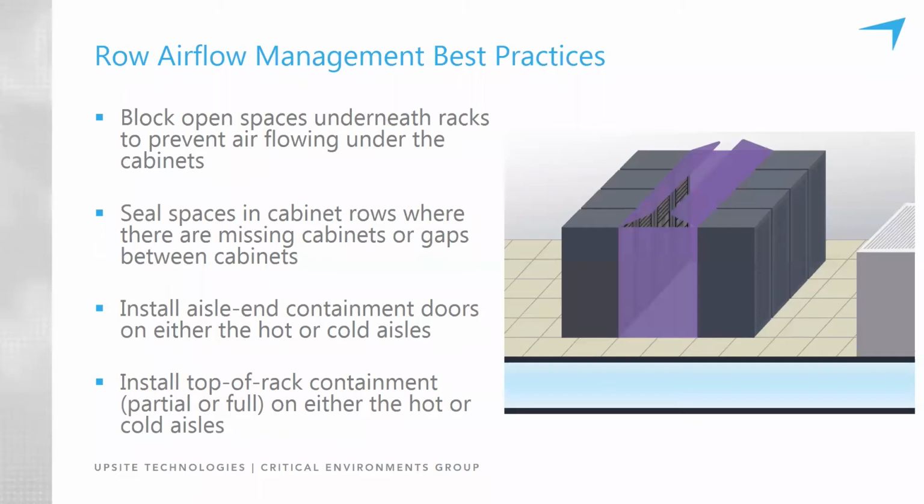And lastly, the top of rack containment. So hot aisle containment typically features an above rack barrier around the perimeter of the hot aisle and typically extends upwards from the racks to the top of the ceiling, or vice versa from the ceiling down to the top of the racks. And cold aisle containment could involve a roof or a capped aisle or even a partially capped aisle that spans across the cold aisle. And again, more to come on both of these as we get into the presentation.